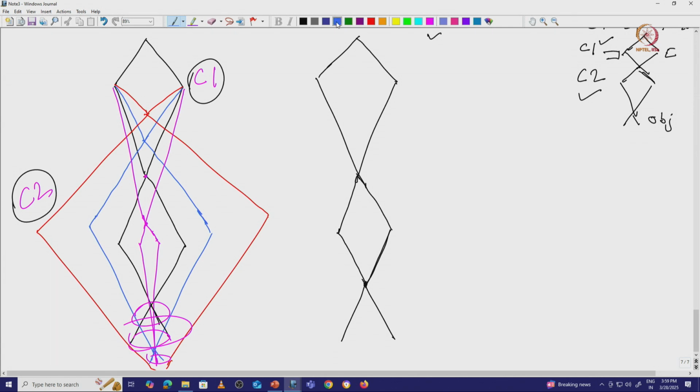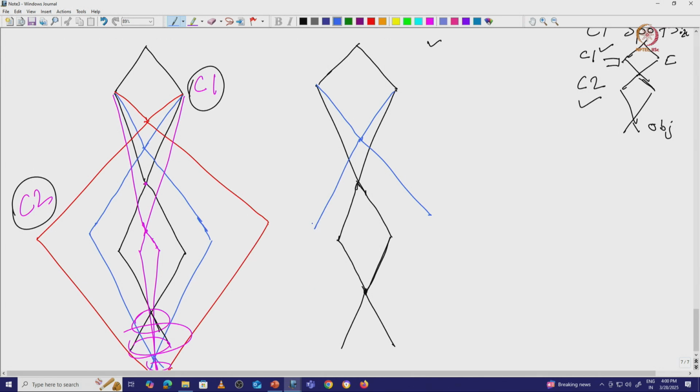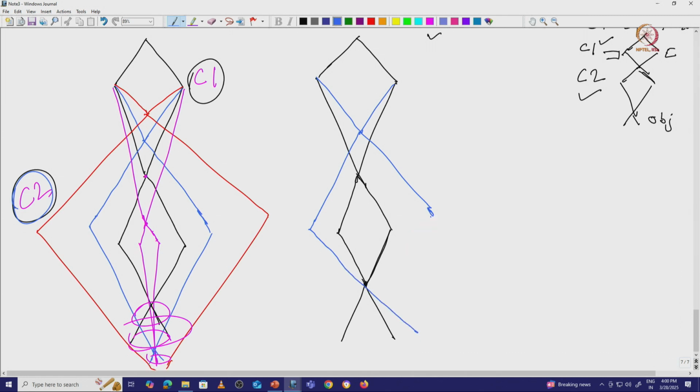Now, there is a second ray. If there is a crossover point here, it will spread the beam, and when the beam is spread, we need some extra care in using the C2 lens current. We have to increase the C2 lens current so the rays can go through this particular center. So if we consider this, it is going through this one.